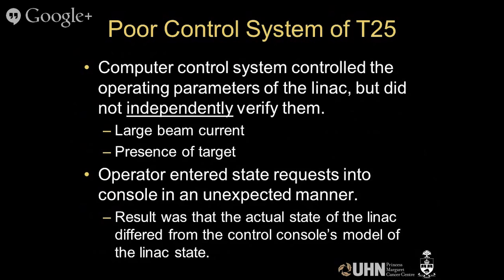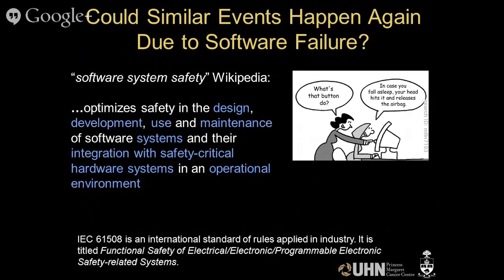So the operator entered state requests into the console in an unexpected way, and the result of that was that the actual state of the Linac differed from the control console's model of the Linac state. So in tomorrow's lecture on patient safety, we're going to get into the concept of the model or the state of the machine: what the operator thinks the machine is, what the designer thinks the machine is, and what the machine actually is. And those states are not always the same, and that's when you can have dangerous situations. So I'll just pass it back now to Brian to finish off with some final thoughts.